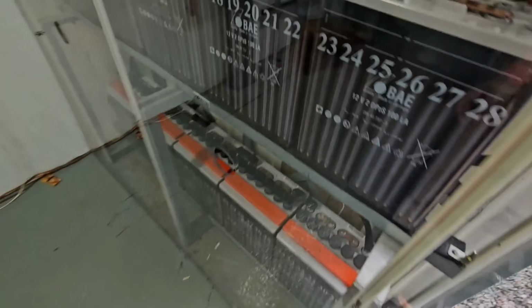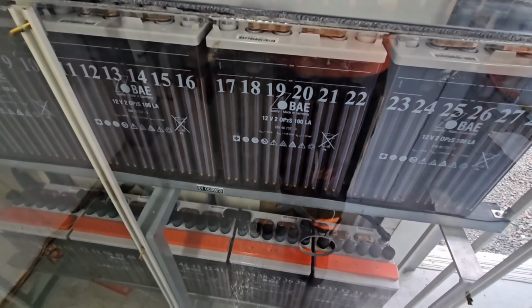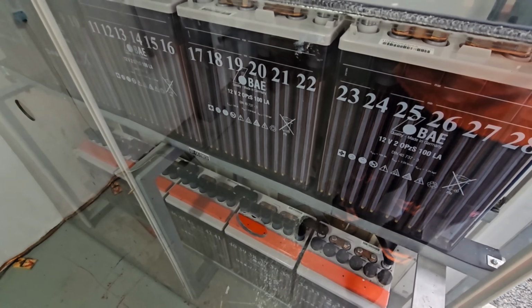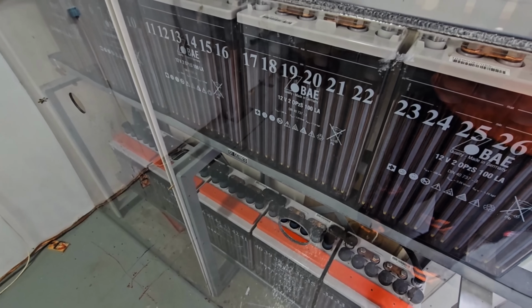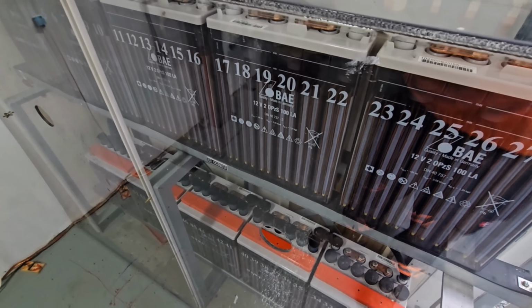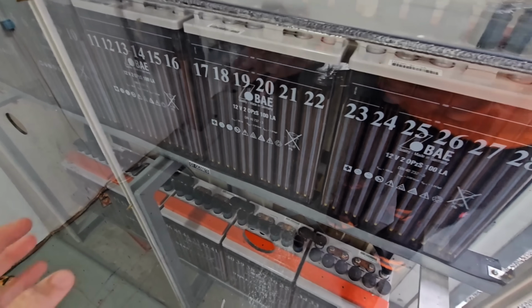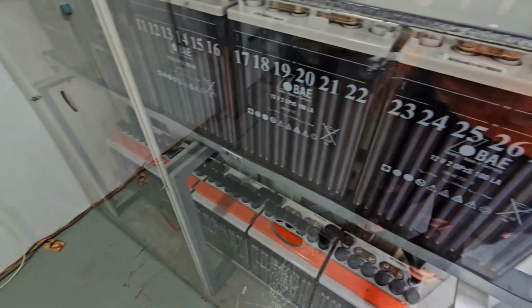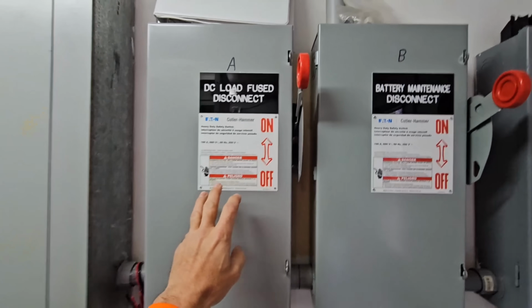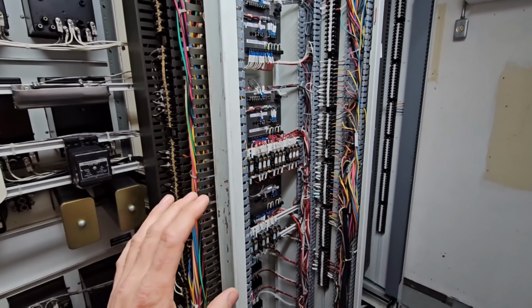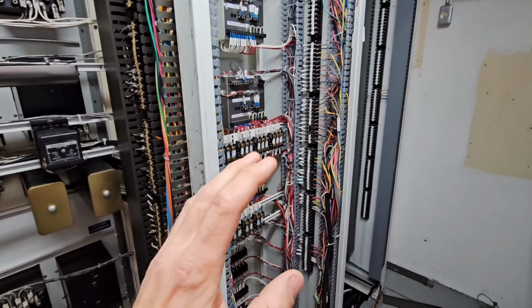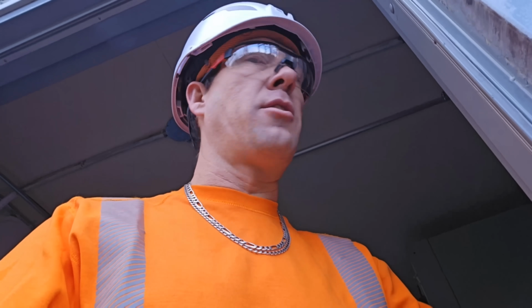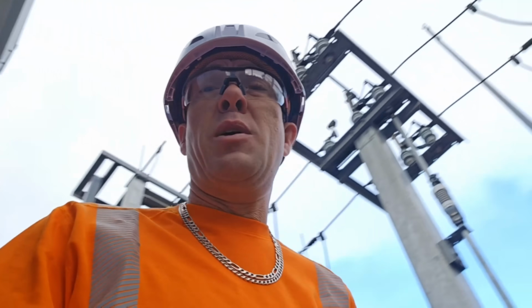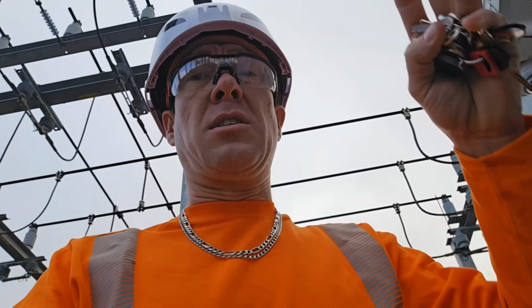Another thing we have to do: our entire operations within this building are backed up through DC batteries. There are multiple backup AC feeds from the grid, but the whole town was out, so all of our backups were down. So we do have a backup with a battery bank. What we do is disconnect the batteries from this system so that when we go to return everything to normal, there's still enough power to operate all these devices. That whole process might have taken another, I don't know, maybe 45 minutes or so. We've got that whole system isolated.